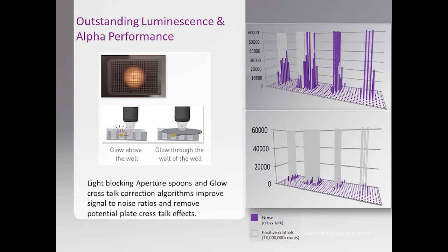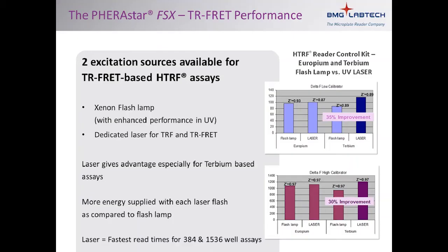We also offer solutions for dealing with common problems like glow crosstalk that you may see in luminescence assays, whether kinetic or endpoint reads. Cross-talk can come from either above the well in a glow luminescence assay or through the side of the plastic itself. With the PHERAstar FSX, we have apertures built in to be able to correct or eliminate light from traveling across the plate going into the detector. We also have algorithms where high background wells caused by glow coming through the plastic can be eliminated by using our algorithm and tests to establish these effects on the microplate.